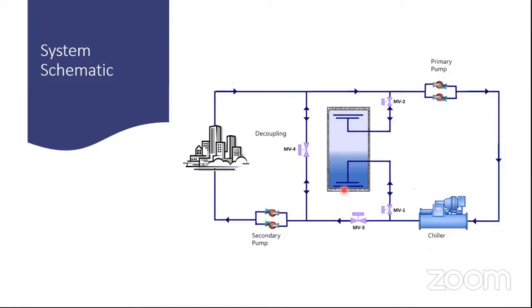Now we should also understand how charging would take place in the same schematic. In a charging mode, charging is possible two ways. There can be a charging only mode in which the chiller is only charging the thermal storage tank and not supplying to the load. Although it is also possible that the chiller is supplying to the load as well for cooling, and any surplus capacity available with the chillers, it can charge also, because charging too will happen from the bottom. From the chiller, see the water coming out and going back to the tank bottom, and the warm water is coming back from here and going to the primary pumps and again being sent into the chiller.